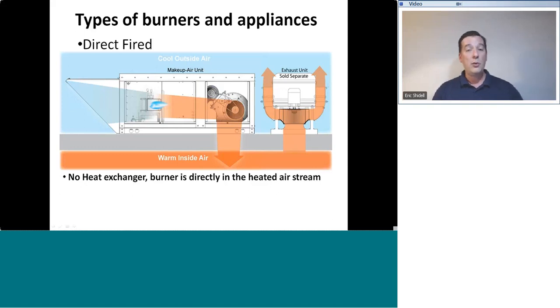Sounds great. In the wintertime, that air can be extremely cold. Below zero if you're in parts of North Dakota and Montana and Minnesota and other places. Very, very cold air. And that will very quickly freeze the kitchen or freeze an area solid. So we cannot have just cold air being dumped in. So we have to heat that air up. And one of the easiest and quickest ways that that is done is with the application of a direct-fired burner. Direct-fired indicates that there is no heat exchanger. The fire is directly in the heated air stream. So all of the products of combustion are heating the air that's being brought in.